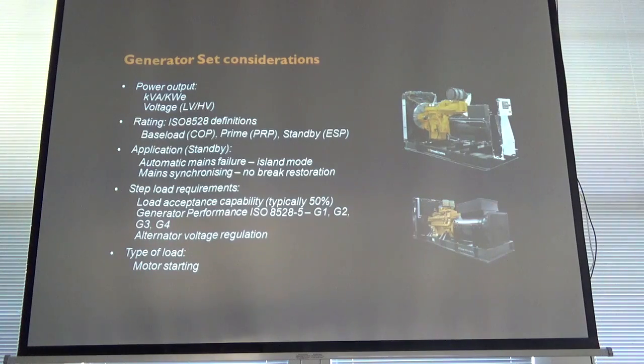The concern you've got is if that tank is not a sufficient reservoir, under certain running and load conditions, your spill return, high temperatures, light load conditions, that fuel will be returning at elevated temperature. You'll get a creep up on the fuel temperature if your reservoir is small, and you can actually get pre-detonation issues. So I always say, 4-hour day tank unless situation and circumstances dictate otherwise. And it could be a belly tank, day tank.